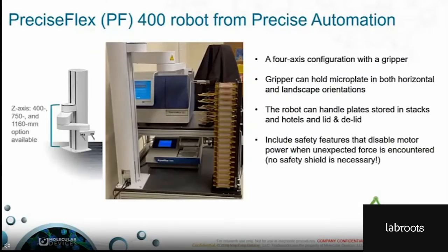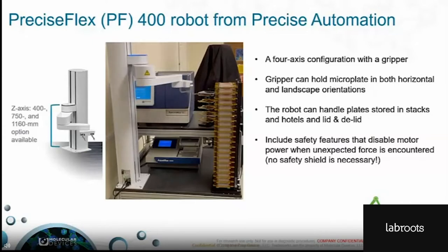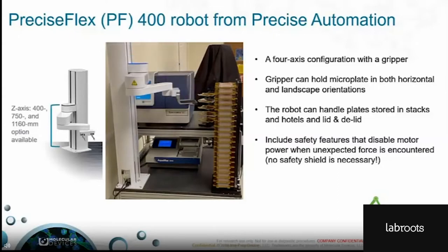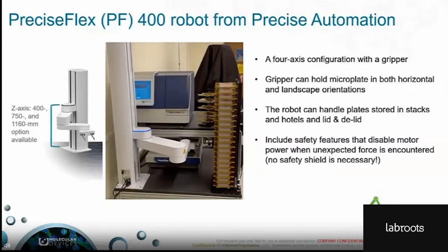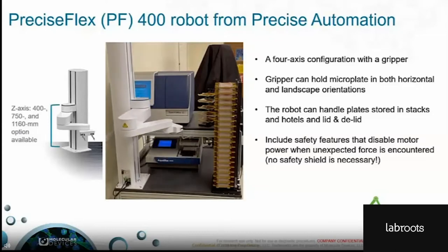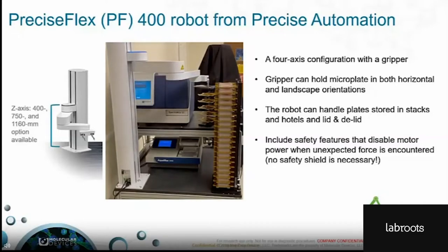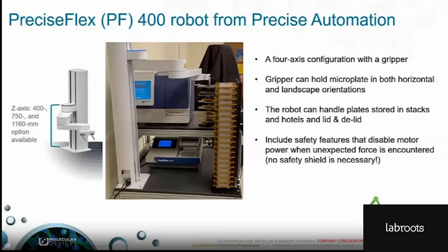The PF400 robotic arm is a four-axis sample handler with a microplate gripper, ideal for automation applications where ease of use, space requirements, and safety are critical. These robots are available in three different height configurations and can be integrated to a linear rail to service both single and multi-station work cells. The gripper allows the robot to handle a wide variety of microplate sizes without needing to change the gripper tool. The PF400 includes advanced safety features that disable motor power when unexpected force is encountered, allowing operation without safety shields in benchtop applications.